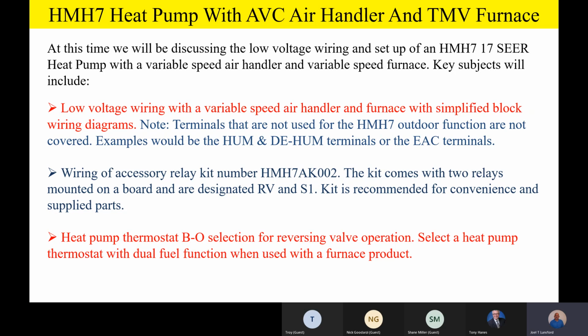Now, please remember, a heat pump thermostat with a B/O selection is still going to be required for reversing valve operation, and we're also going to have to have a heat pump with dual fuel function if you're going to use it on the furnace product.